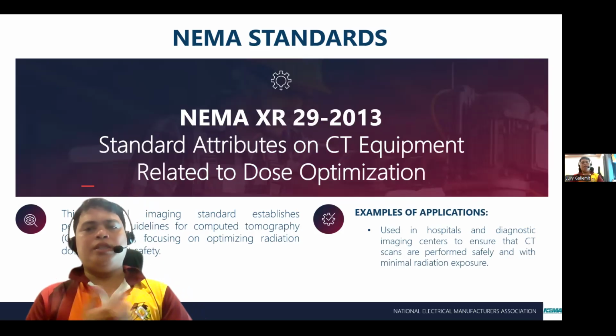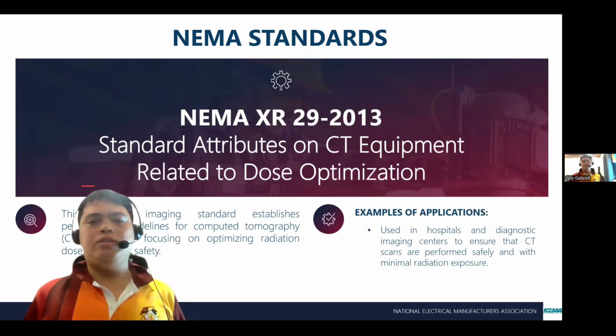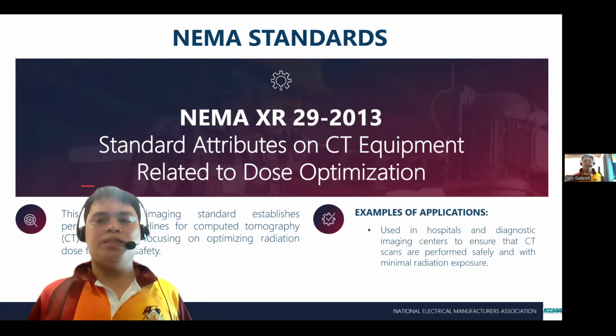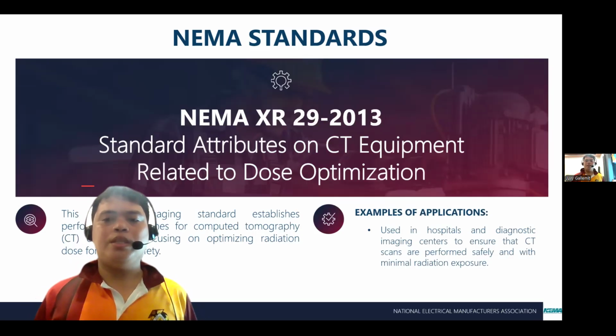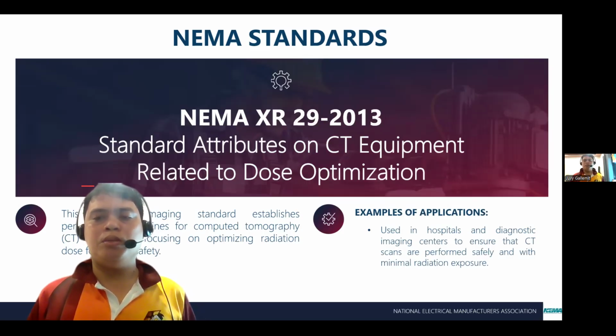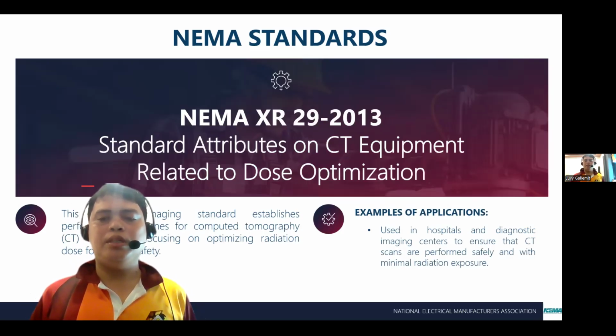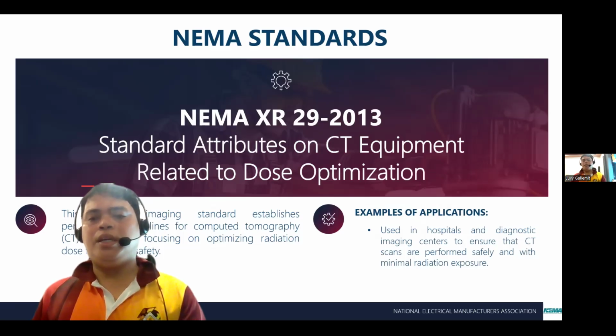So, also known as the standard attributes on CT equipment related to dose optimization, it establishes specific technical features that computed tomography (CT) scanners must have to support radiation dose reduction and improve patient safety.